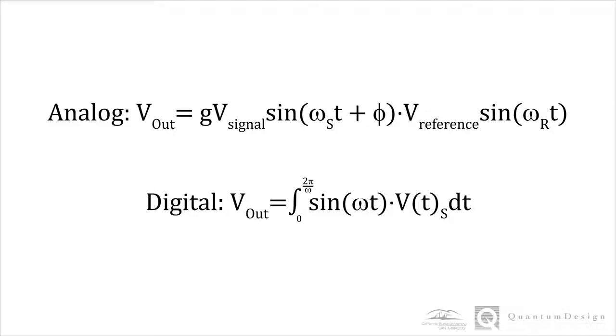Instead of a mixer in a digital lock-in amplifier, the input signal is integrated with a digitally created reference sine wave over one cycle in order to obtain the lock-in result. This has the advantage of being so accurate as to not have the extra harmonics that can be present in an analog reference signal.